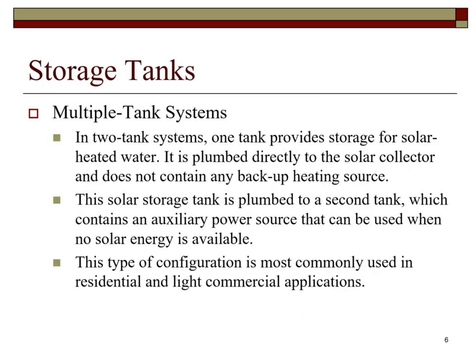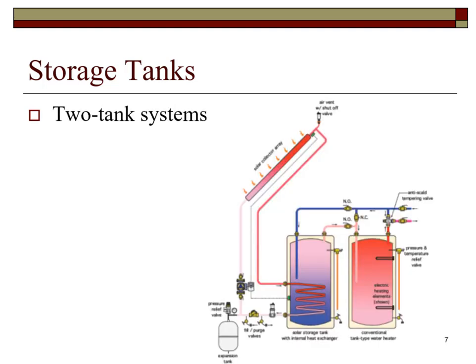The 2-tank system as described is a more common type. The first tank has a heat exchanger and the water is heated by the solar thermal collector. This tank then supplies preheated water to the second and regular water heater. This configuration allows, when the water is not heated to the desired temperature by the solar thermal collector, the water will be heated to the desired temperature in the second and regular water heater. A picture of the 2-tank system described is shown here.